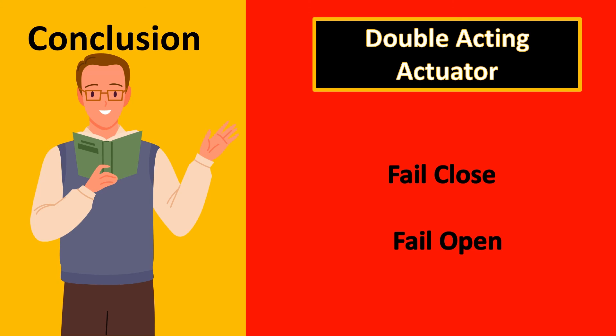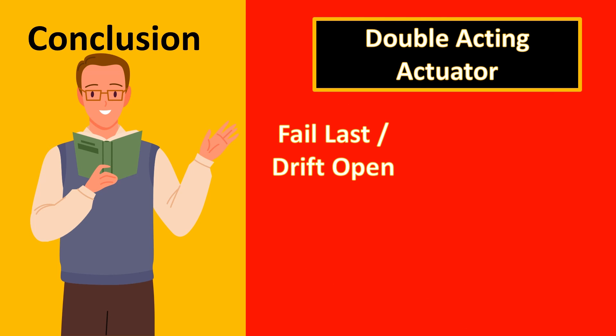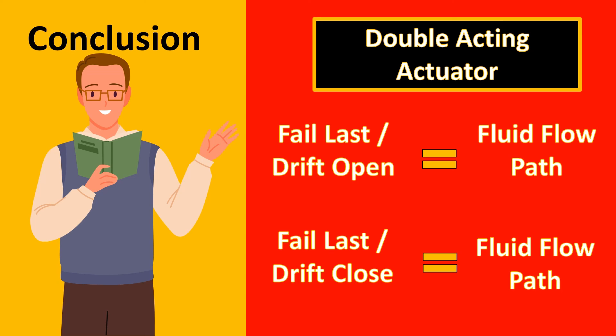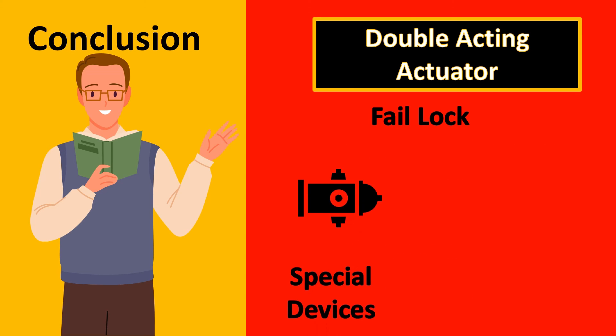If it is a double acting actuator do not mention just fail close fail open. Usually you have to come up with the option such as fail last drift open, fail last drift close and remember the flow should always assist the failure mode. Finally, there is something called as fail lock where you use special devices which are added to control valve which actually protects the air or the fluid inside to trap out. So the last position is where the control valve is locked.